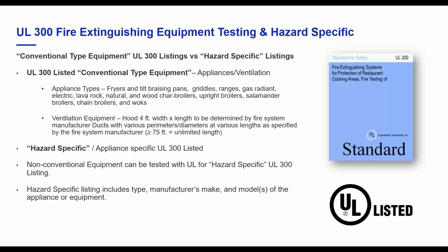for filtration, ductwork, what those lengths are, how to test them, and then also the hazard-specific coverages that I touched on. So anything that doesn't fall in the first two bullets will typically fall into the hazard-specific. Those are appliances that you want to have a more efficient coverage on, maybe a more specific nozzle location, or maybe something with an obstruction. And then there's non-conventional equipment that can be tested to UL. So you can bring any of those appliances that don't fall in the first three bullets. And UL, how do we test this? The approval agency puts together a full-scale test plan to validate the coverage is adequate should that system be called upon.